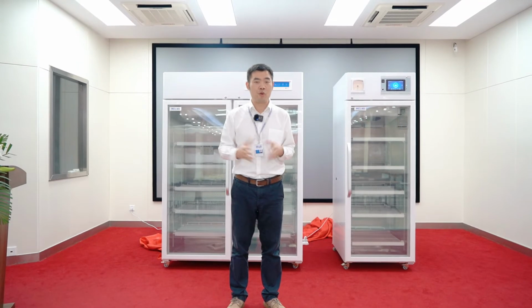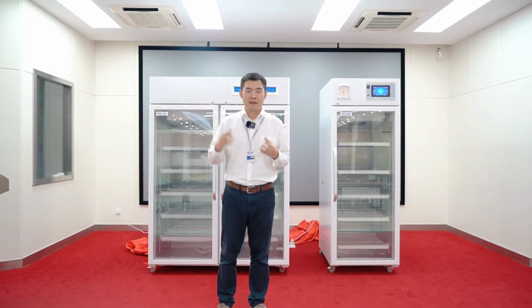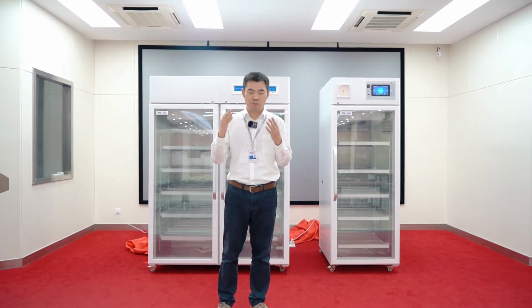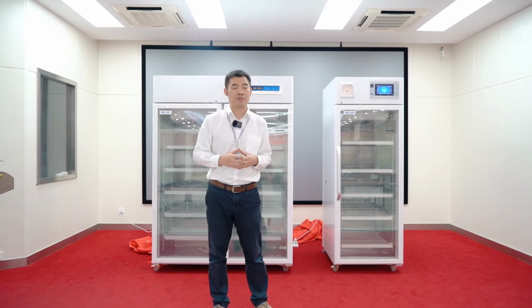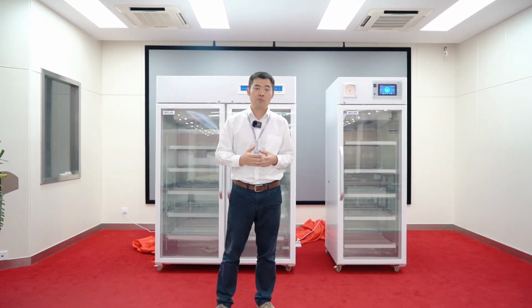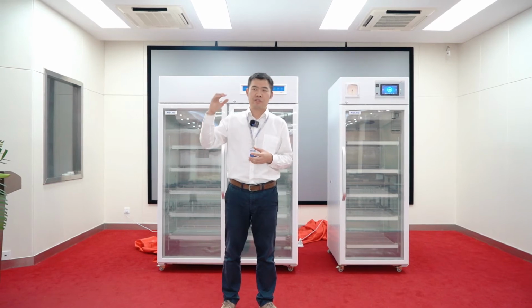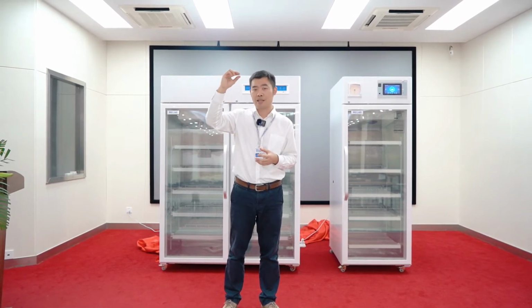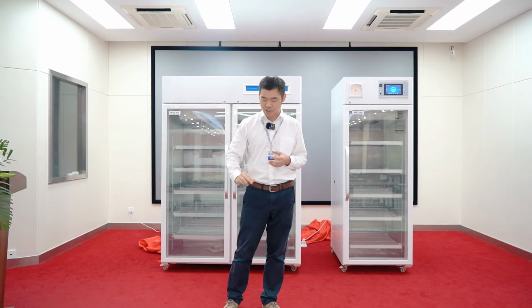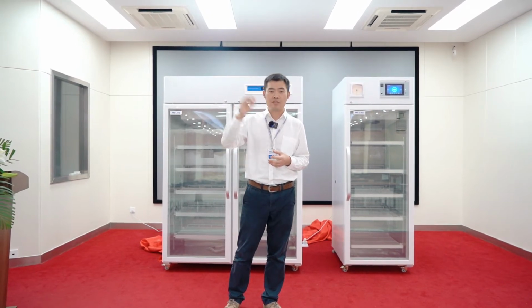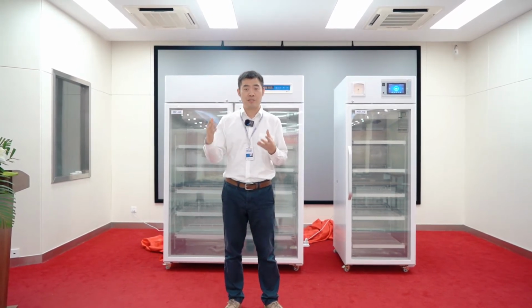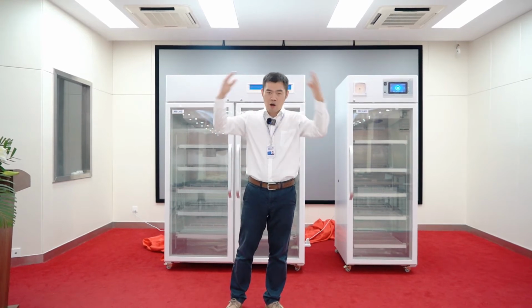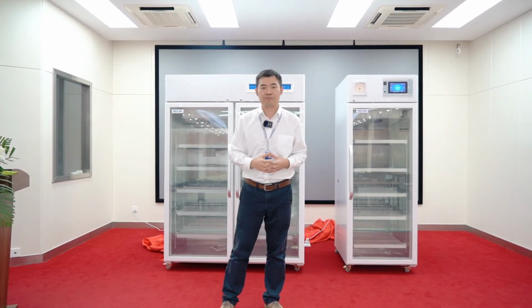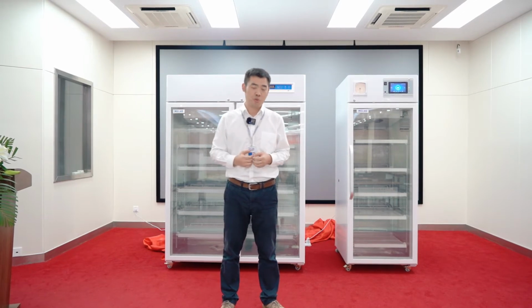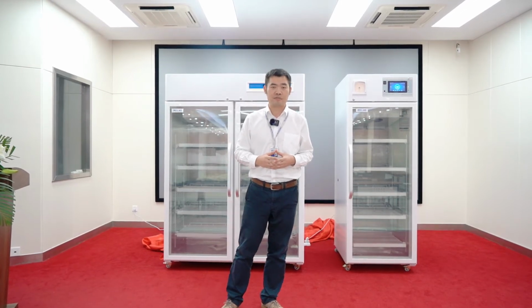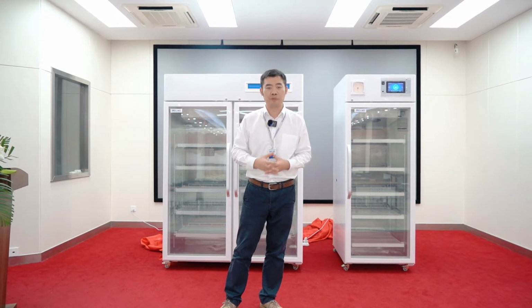Also, uniformity. That's the key thing customers really worry about. They want to know, if you measure the temperature at the top of the cabinet and at the bottom of the cabinet, what the variation from the set point is overall in the cabinet. So you really need a good, consistent temperature throughout the chamber.